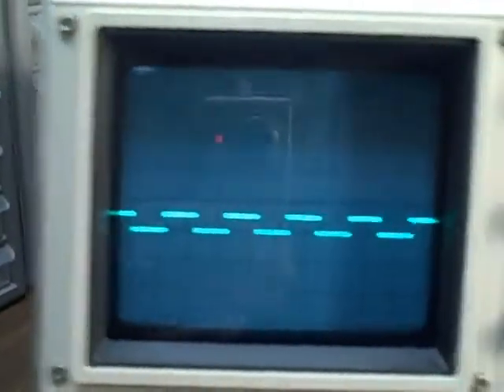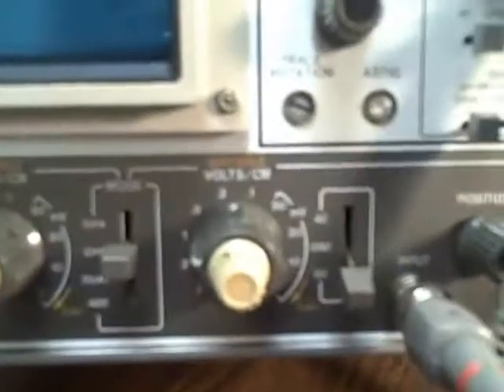Alright, we now have channel B connected to the same calibration point, and we are looking at channel B on the screen, and we're going to go through the same steps. We are currently set at 1 volt per division, and we see that we are up a half a division. If I go to a half volt per division and adjust for my 0, I'm coming up 1 full division. 0.2 volts per division, and I rise 2 1/2 divisions. 0.1 volt per division, and I go 5 divisions.